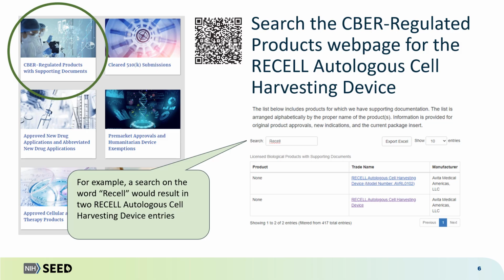The CBER Regulated Products webpage offers access to these databases. For instance, the RECELL autologous cell harvesting device requires review from both CBER and CDRH as it qualifies as a biological product and a device.